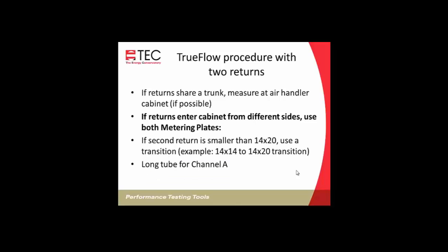If you're using the DG700, it's helpful to have a long tube for the channel A operating pressure that will reach both of the locations where you're taking measurements from. And that way you can use that function where you enter the normal system operating pressure into the system, and you can use one gauge and take your flow readings separately and add them together. You know, the adjusted flow from the first grill and the adjusted flow from the second grill, and add those together.